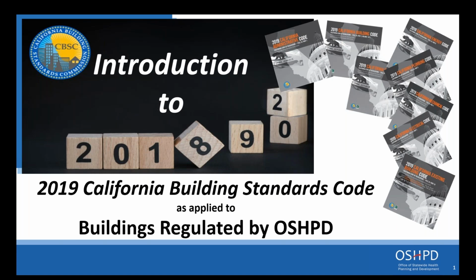OSHPD's requirements were, as shown, 24 hours for hospitals, 72 for hospitals with NPC-5 ratings, and then 6 hours for skilled nursing, 4 hours for ambulatory surgicals. Those requirements can be found in Article 700.12(B).